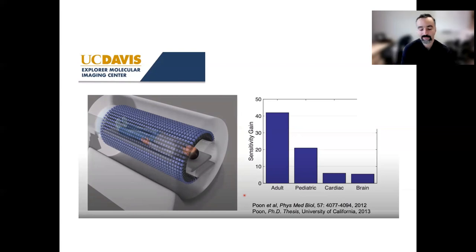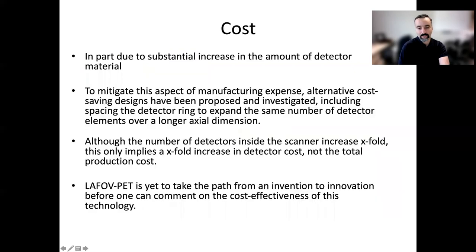With the Siemens scanner, time-of-flight is very good, and even though it's not included within sensitivity assessments, it effectively has a major impact on image quality. So, give or take, we're talking about an order of magnitude enhancement in sensitivity — roughly speaking, as a guide to move forward.